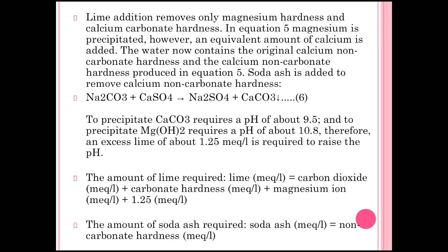When soda (Na₂CO₃) is added to water containing calcium sulfate impurity, sodium sulfate is released and calcium carbonate precipitate is formed. So when Na₂CO₃ reacts with calcium sulfate it gives sodium sulfate plus calcium carbonate precipitate. The precipitate of CaCO₃ requires a pH of about 9.5 and the precipitate of magnesium hydroxide requires a pH of about 10.8, therefore excess lime is added to raise the pH so the reactions are possible.